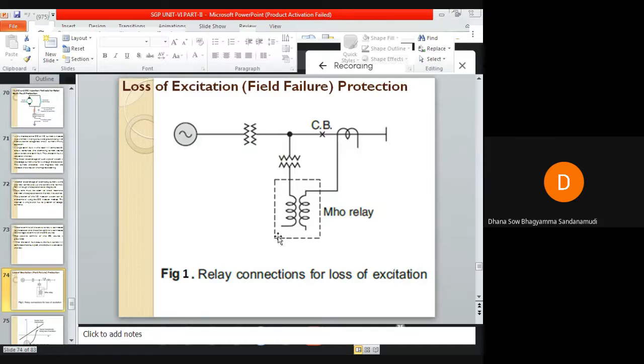This offset Mho relay is operated by AC currents and voltages at the generator terminals. The relay setting is so arranged that the relay will operate whenever the excitation goes below a certain value and the machine starts running asynchronously. Why? Because during asynchronous operation, the rotor gets heated up.